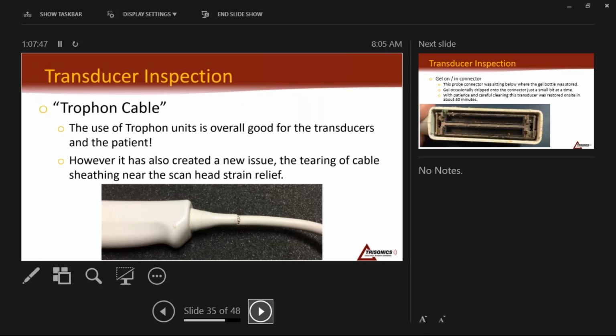One of them is the clip that holds the transducer. There are 2 clips, a small and a big one. In ultrasound, generally we just want the bigger one. Also, if the Trophon is mounted a little high, when the sonographers go to grab it, they're grabbing that cord and pulling down to pull it out, and that's causing problems. We really want that Trophon countertop high, not wall high, so that it's right there in front of us, so they can pull that straight out.